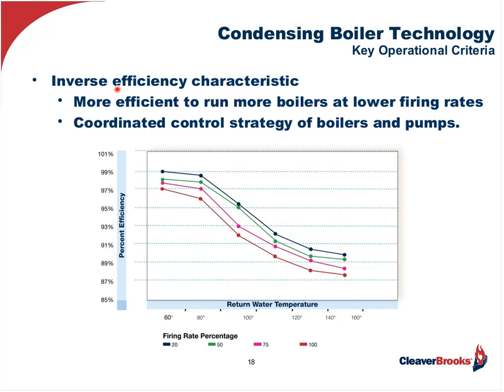The other unique characteristic of condensing boilers is you want to run them at lower firing rates. So for the same water temperature, say you have 120, you'll notice you go from 89% to 91%, about a 2% increase. Everywhere across the range, by going from 100% to 20% firing range, you will pick up 2 to 3%. Not a major increase, but again, if you're doing your LEED certification and doing your energy modeling, every small percentage point helps. And those of you that have done the modeling and tried to maximize your points know you're scratching, just trying to dig out anything you can to improve your alternatives to maximize those points.